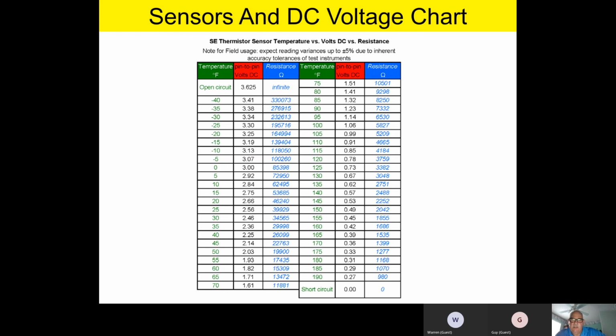Now, it should be noted, it should be within about 5%. And so if you're within about 5% of the chart value, you're plenty close. It should be noted that at 75 degrees, the nominal calibration point for our sensors is right at 10,000 ohms, or very, very close to it. So that's something you can drill in your brain. If I take any of the sensors on my simplicity control and subject them to 75 degrees, they should read around 10,000 ohms.